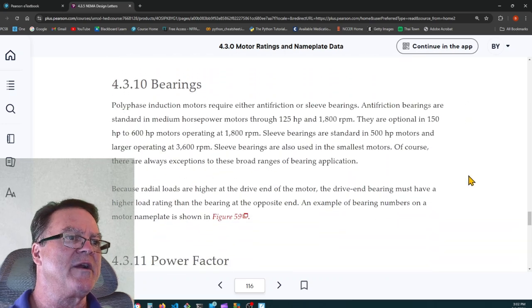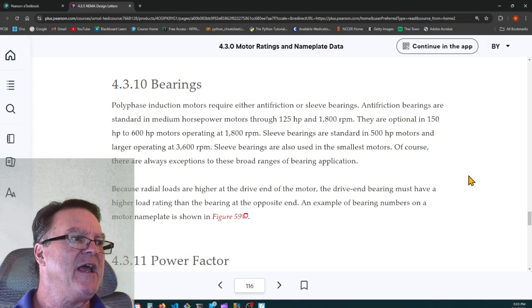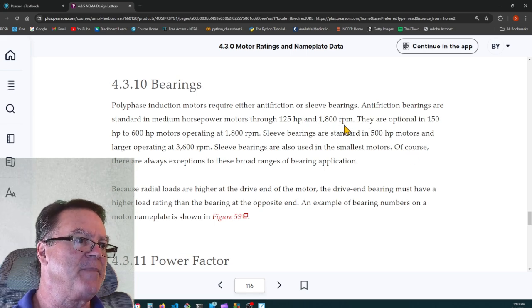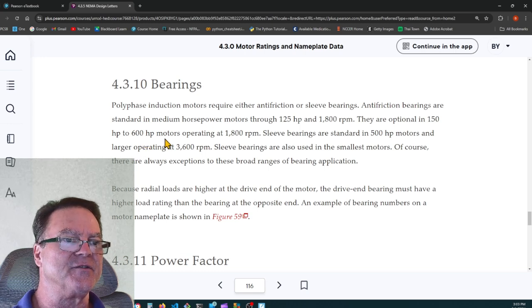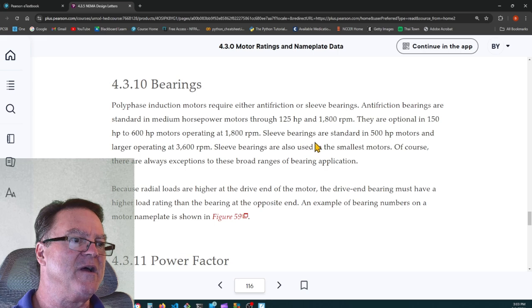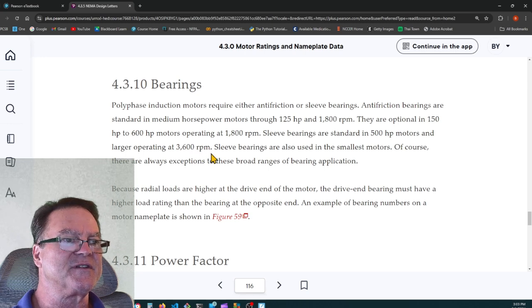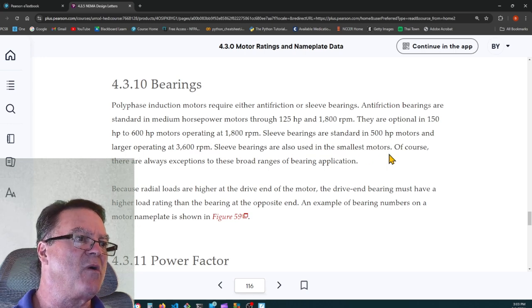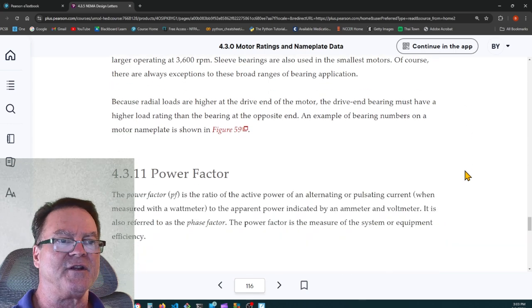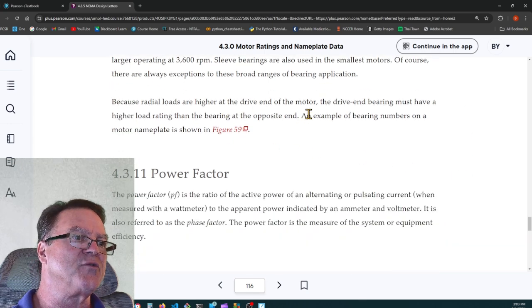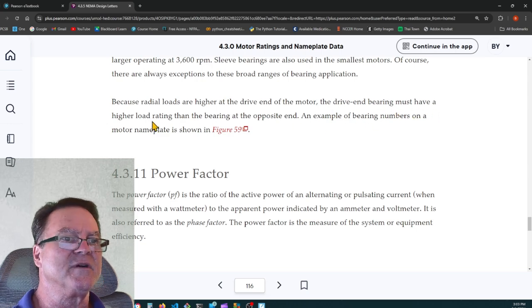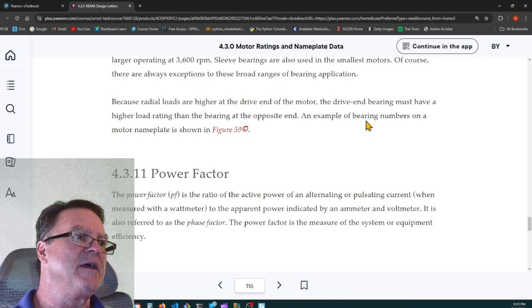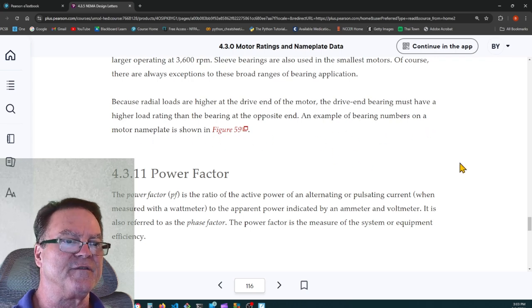Bearings. Polyphase induction motors require either anti-friction or sleeve bearings. Anti-friction bearings are standard in medium horsepower motors through 125 horsepower and 1800 RPM. They're optional in 150 to 600 horsepower motors operating at 1800 RPM. Sleeve bearings are standard in 500 horsepower motors and larger, operating at 3600 RPM. Sleeve bearings are also used in the smallest motors. Of course, there are always exceptions to these broad ranges of bearing application. Because radial loads are higher at the drive end of the motor, the drive end bearing must have a higher load rating than the bearing at the opposite end. An example of bearing numbers on a motor nameplate is shown in figure 59.